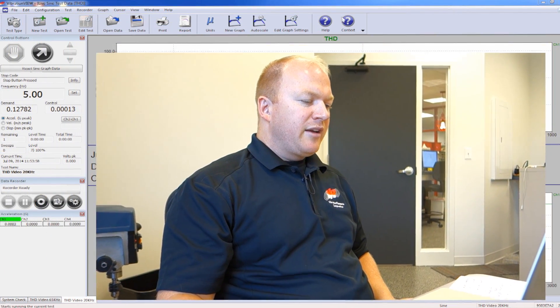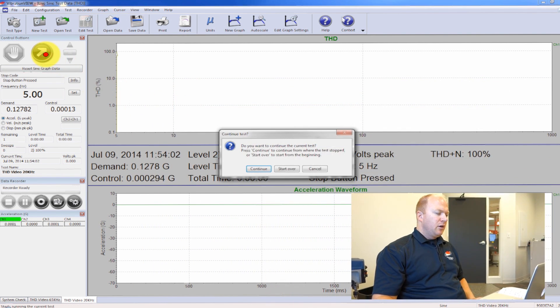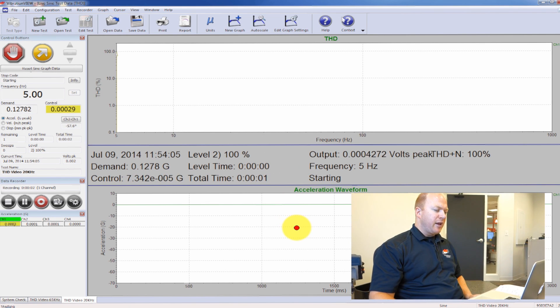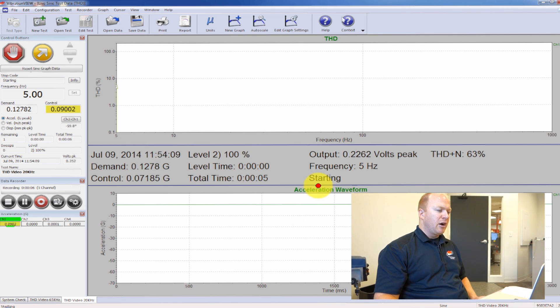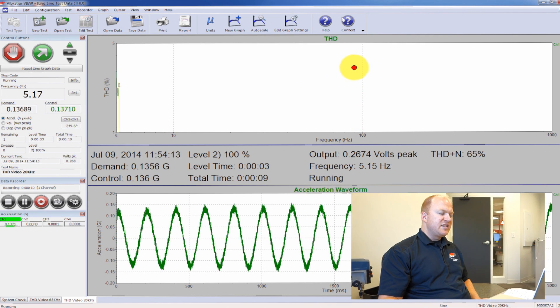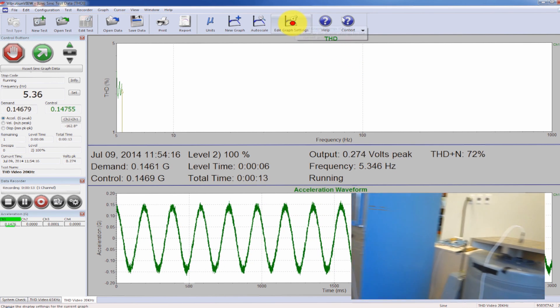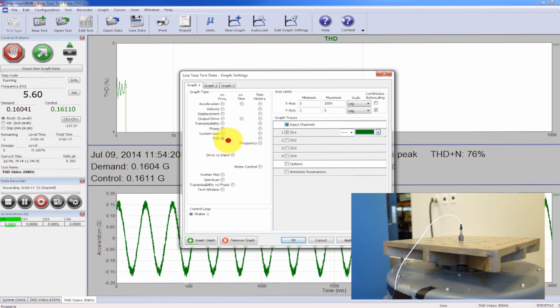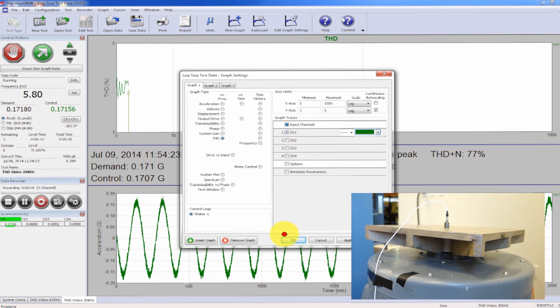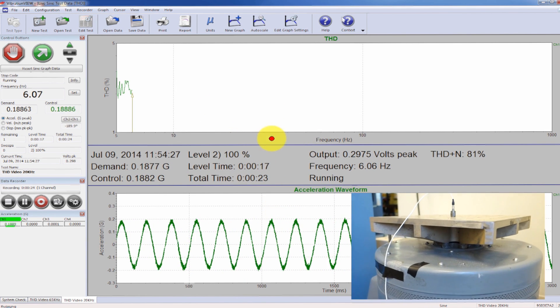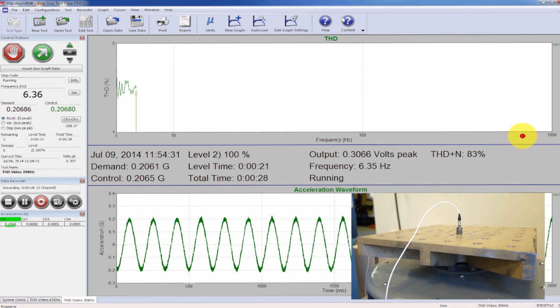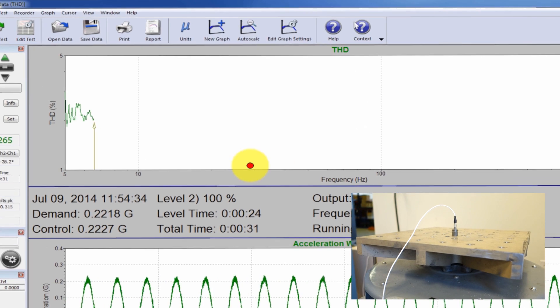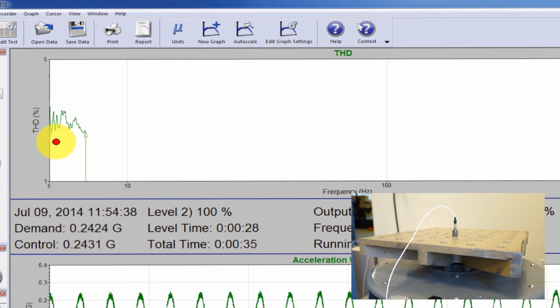So I'm ready to run my sine sweep. I'm going to hit the run button here. It takes a second to come up like every other test. But you can see I have a couple of plots up that are applicable to what I'm interested in. One is the THD. If I click the edit graph settings, I have the THD selected for my graph type, and I'm just looking at channel one, which is my control channel. So it's giving me the frequency range that I'm operating at for this test, which is 5 to 1000 hertz. And the THD is a percentage of that signal.